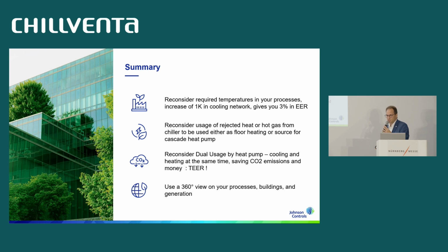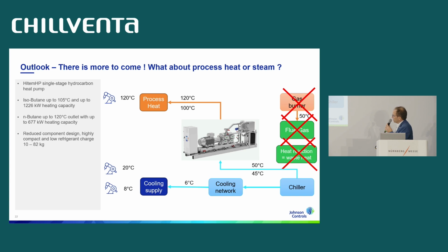As you might have seen, there was always the steam which was not fulfilled by our systems, but now here the steam comes into place again. So the outlook, there's more to come. If you have waste heat at a level of 40 or 50 degrees Celsius, you can easily heat that up to 120 degrees process heat. So this is a new product from us. It's our high temperature heat pump, shown also on the booth, working with natural refrigerant hydrocarbons, so isobutane and n-butane, with a very reduced component design and low refrigerant charge. So if you are thinking about cooling and heat rejection, you can also think about process heat.